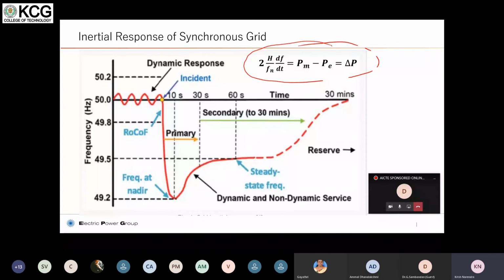What is shown in the graph is a region where the frequency falls freely. That means there is no support from any control, such as governors or frequency control methodologies, primary, secondary, or tertiary control of frequency. Nothing happens in the system, so the frequency falls freely. This particular time frame is called the inertial time frame.